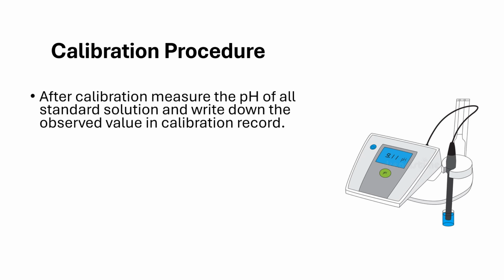So once the calibration is completed, measure the pH of each standard solution to confirm the accuracy, right? And write down the observed value for each solution in the calibration records. This helps to verify that the pH meter is correctly calibrated. When recording the pH values, ensure that they do not differ by more than plus or minus 0.02 from the claimed standard value, right?